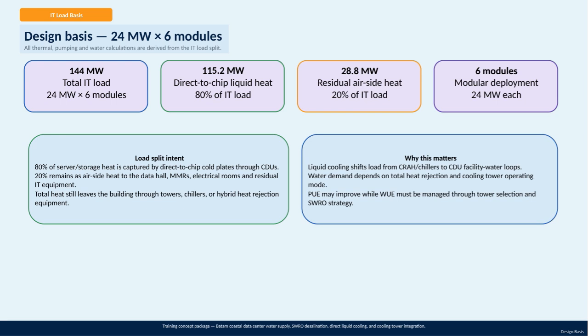The remaining 20%, approximately 28.8 megawatts, is residual heat that leaves as airside heat in areas like the data hall, maintenance and monitoring rooms, and electrical rooms. Even with direct liquid cooling in place, this heat still needs to be expelled from the building, typically through cooling towers, chillers, or hybrid heat rejection systems. Understanding this load split is critical because liquid cooling reduces reliance on traditional air cooling solutions, such as CRAH units and chillers, shifting the load towards facility water loops connected to the CDUs.